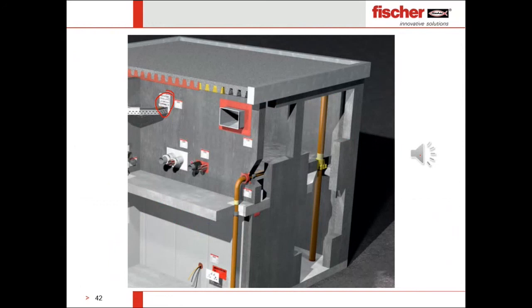So when we have this through penetration, they will ask, this area was a fire zone area. Meaning if fire happens in this part, it should not go to the second part. But unfortunately, because we already break here, when we have a fire in this area, it will go from the hole to the second part. So usually for through penetration, there are systems which can be used to block the fire and smoke from going from one zone to the second zone. So we have to fill this gap with this type of fire sealant.